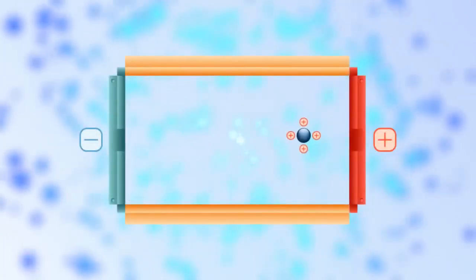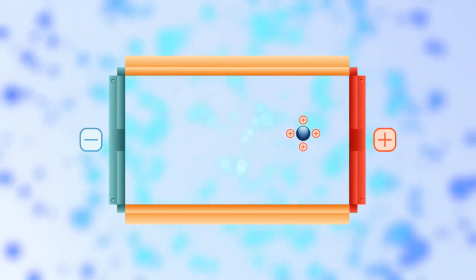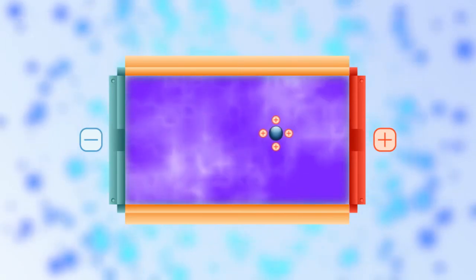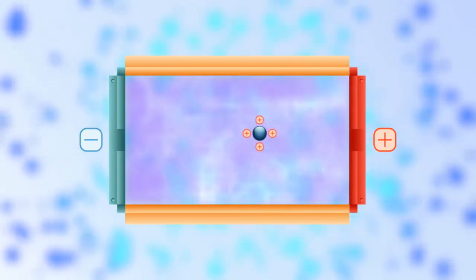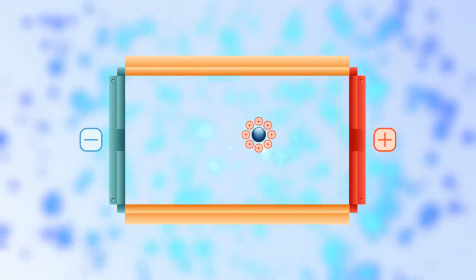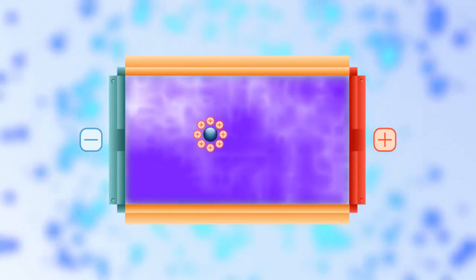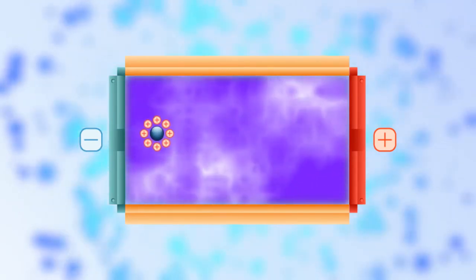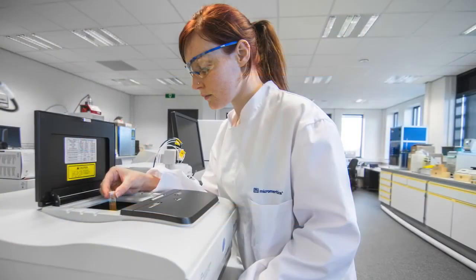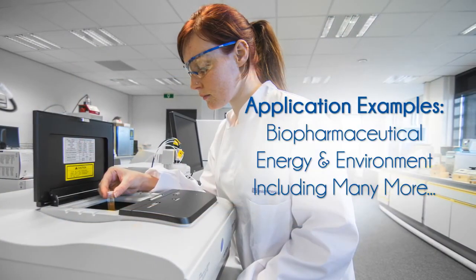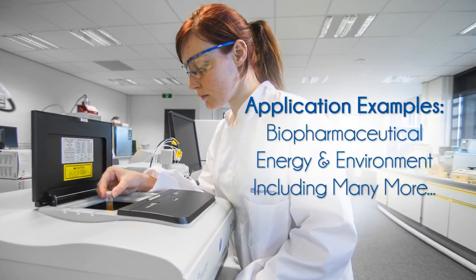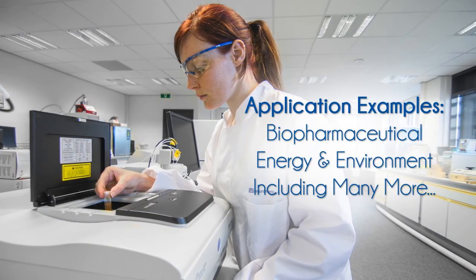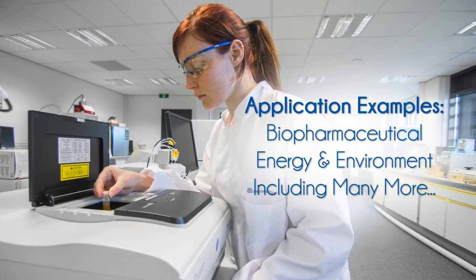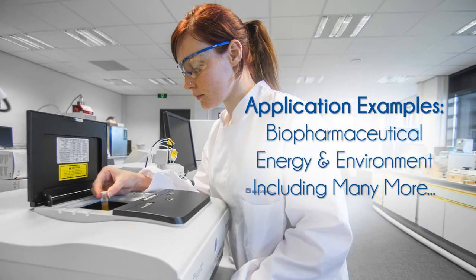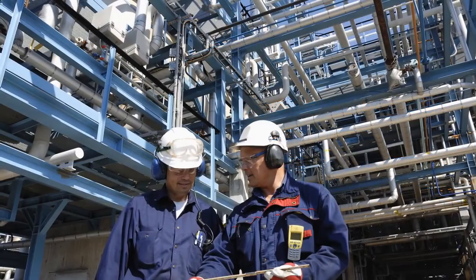The stability of nanoparticle suspensions can be quantified using electrophoretic light scattering. ELS determines the electrical potential, or zeta potential, in the suspension that can cause particles to attract to each other or repel each other. The NanoPlus is a unique tool that can determine both size by backscattering DLS and zeta potential by ELS.